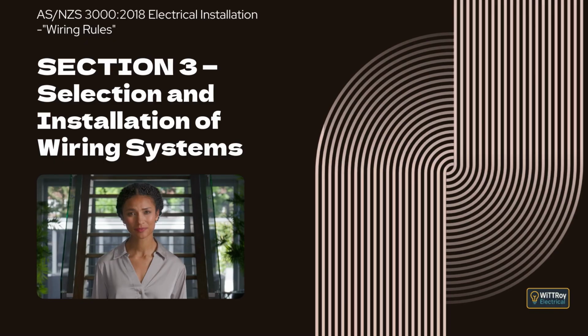Clause 3.7.2.11 Earthing conductors. This clause states that soldered earthing connections must be mechanically secured independently of the solder, and that tunnel-type terminals must be designed to clamp conductors effectively without cutting them. Clause 3.7.3, Joints in cables.